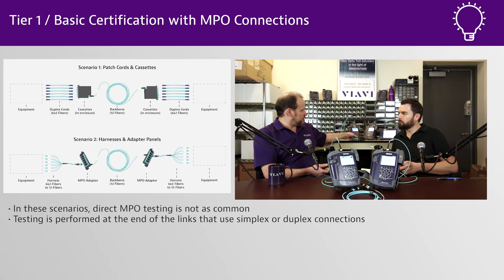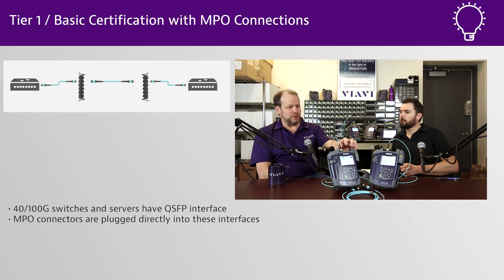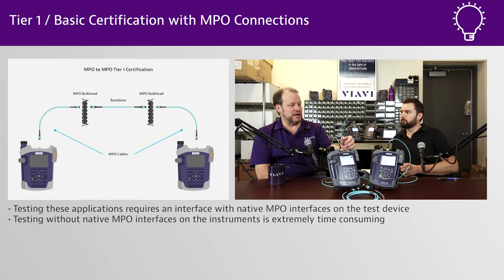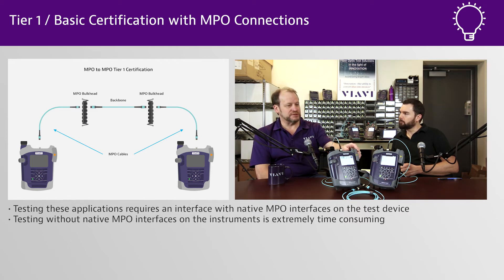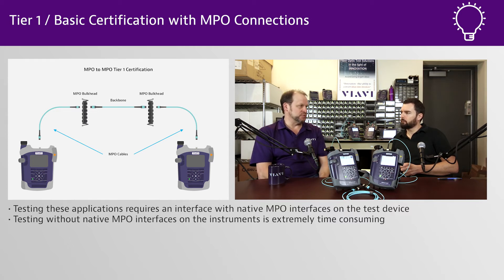Things start to get different when you're running at 40 and 100 gig with multimode, and there are systems like PSM4 for single mode that also run native MPO right into the equipment — whether it's a switch, router, or server. For that, you need native MPO interfaces on your test equipment to test those links and channels. The MPO-LX does your basic or Tier 1 certification — loss, length, and polarity — much the same way as an OLTS on LC links: set reference, set a limit, connect up to the system you're testing, perform the test, and get pass-fail on 12 fibers instead of two.